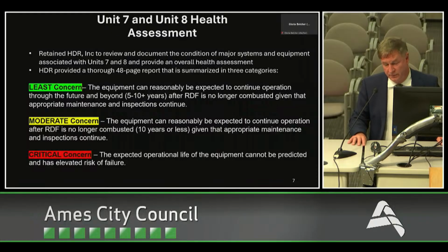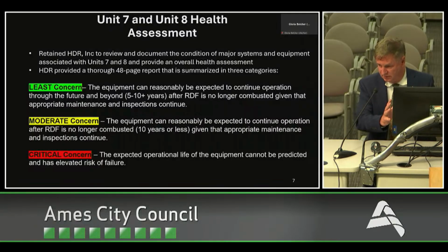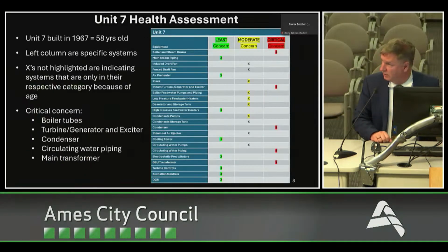Moderate concern, you start looking at that equipment and say, okay, it could fail in 5 years, but we believe it'll keep going for about 10 years, up to about 10 years. And then critical concern is something that we start worrying about, just like you'd have in your car if you've got a low tire. Now the next screen is going to look, well, let's just go there.